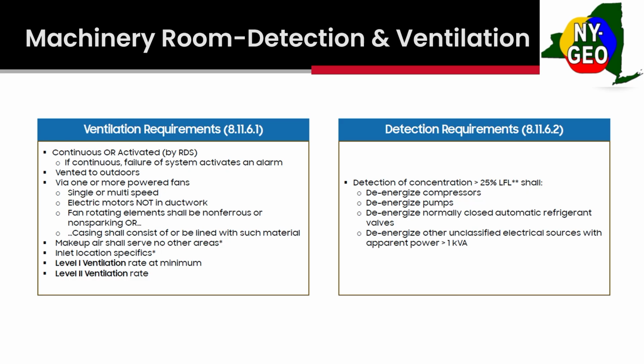So again, it has very strict ventilation rates. Just like in an occupied space, it can run continuously or be activated by alarm, vented to the outdoors. The fans must be separate and have separate power, electric non-spark motors. And for the makeup air, you can't steal makeup air from another area. It's got to have its own makeup air. And the inlets and exhausts have to be low.